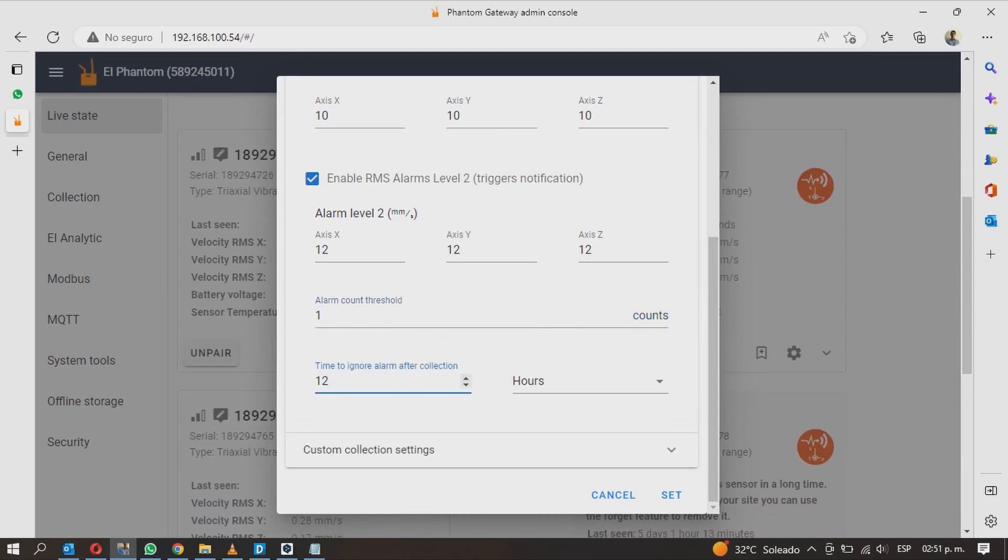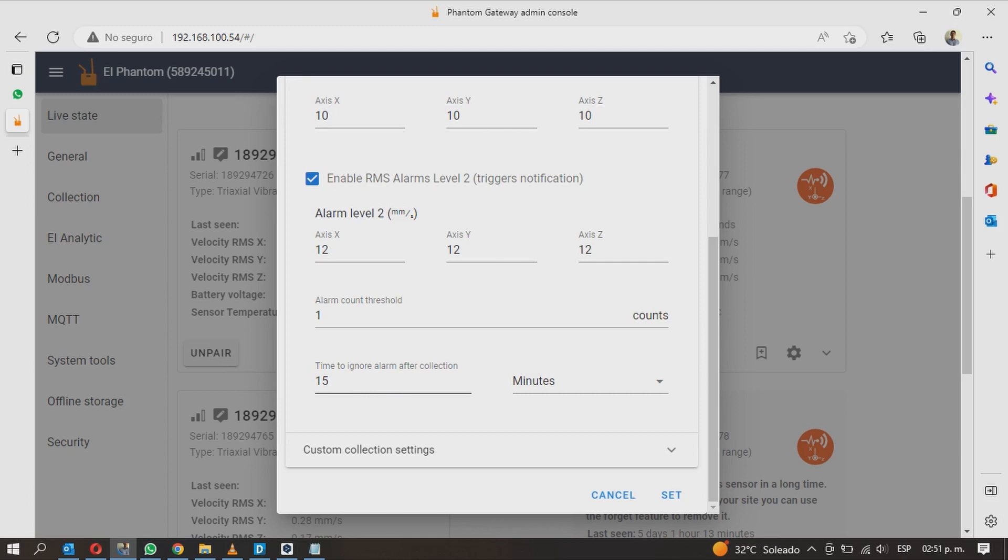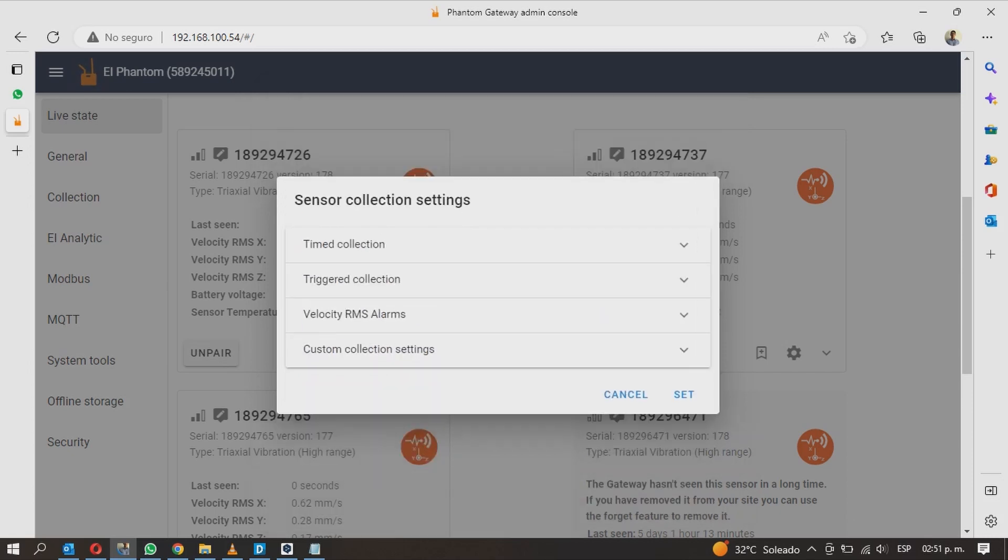Finally you can tell the sensor how much time must pass before it can be alarmed again after an alarm. On the right side change between minutes, hours or days and on the left side enter the value. For example with this configuration shown in the video, if the Phantom is alarmed, 15 minutes must pass before it can be alarmed again. This is just an example and you can choose the value that suits you best.